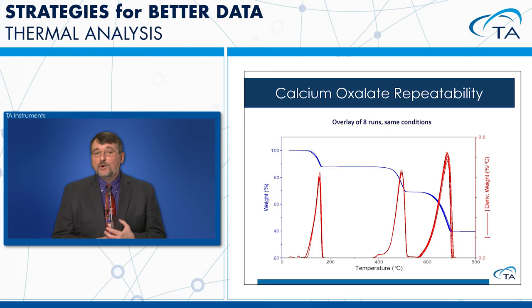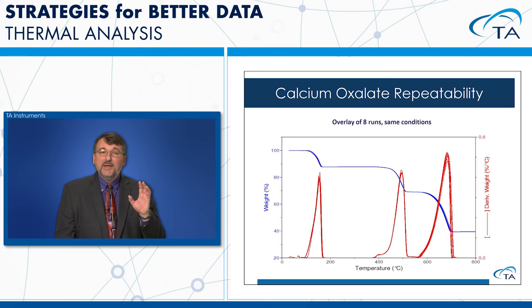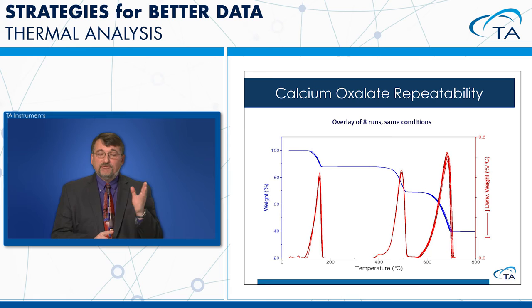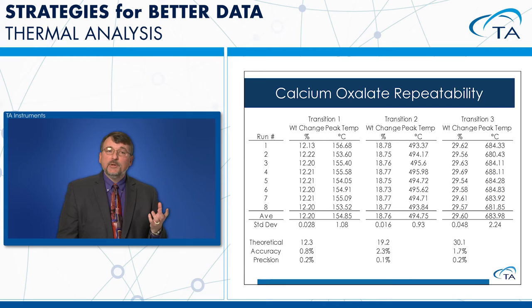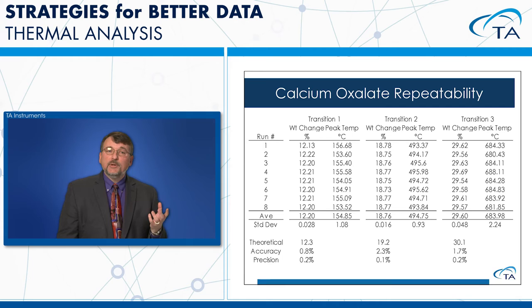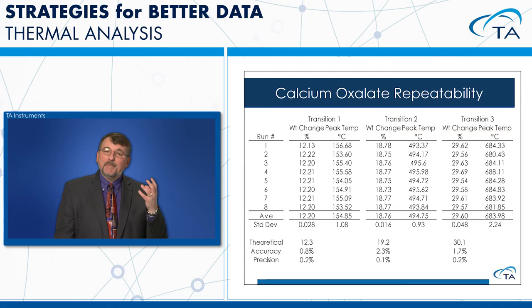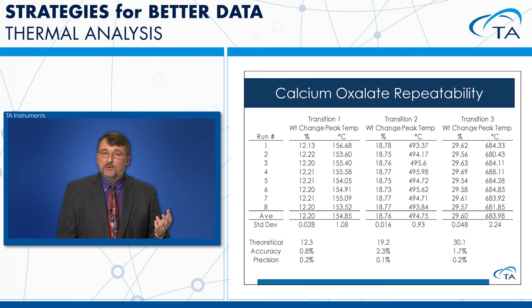On TGA, using calcium oxalate requires repeatability rather than precision since a fresh sample must be loaded each time. Eight runs overlaid show very good agreement, laying on top of each other well. The average and standard deviation of the weight loss steps confirm excellent repeatability. Calcium oxalate is not a calibration standard, but it's a good instrument check — confirming you get the expected weight loss for each step and consistent repeatability.